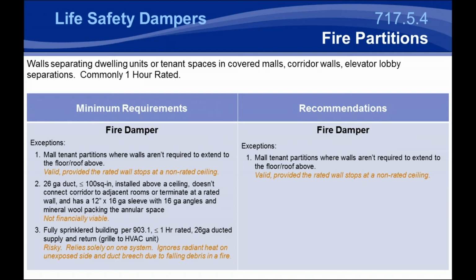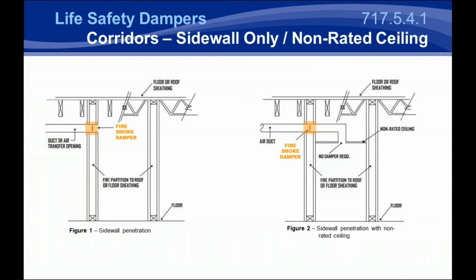Of course, if you've got a fully sprinklered building and you use that 26 gauge fully ducted supply and return with a grill, you can eliminate the fire damper, but we think it's risky, as we talked about earlier, because it ignores the potential duct breach for falling debris in a fire. So typically the most valid trade-off for fire partitions is when that partition does not extend from deck to deck.